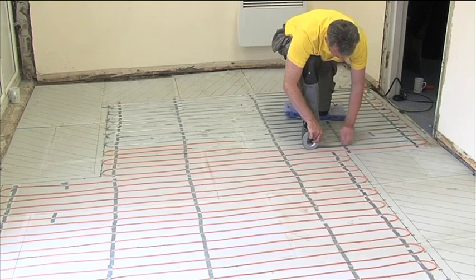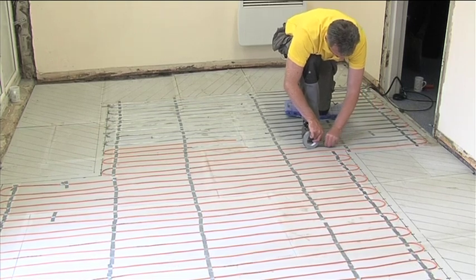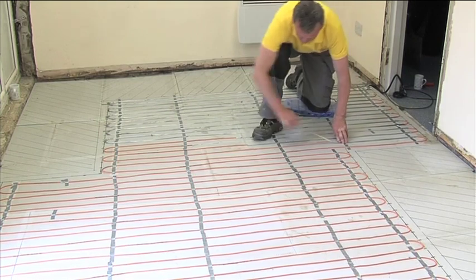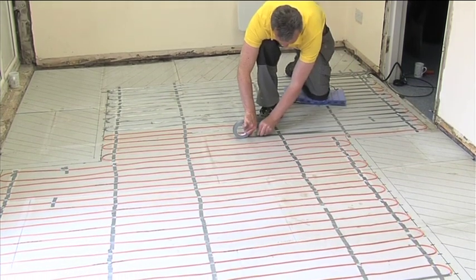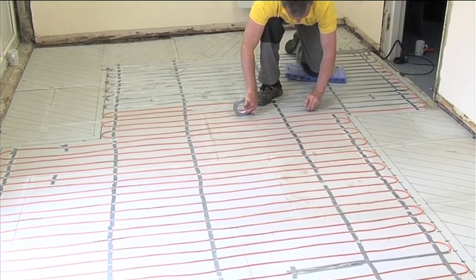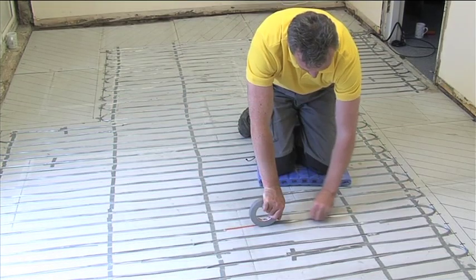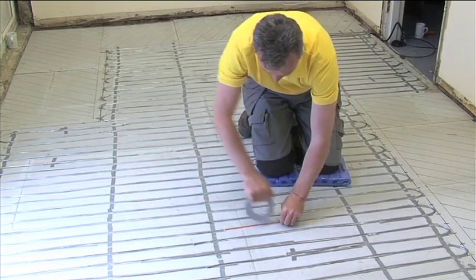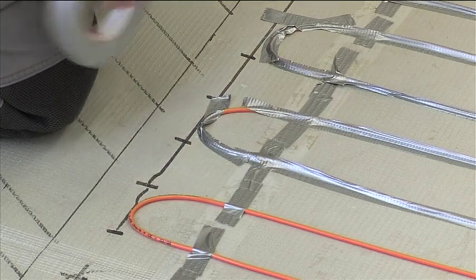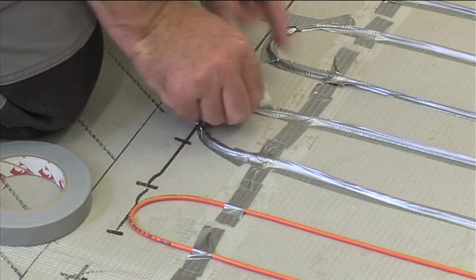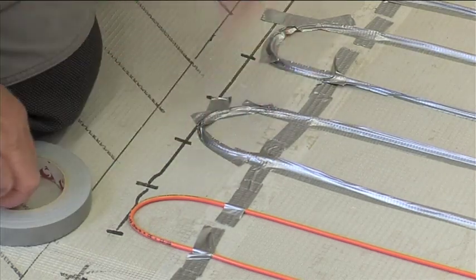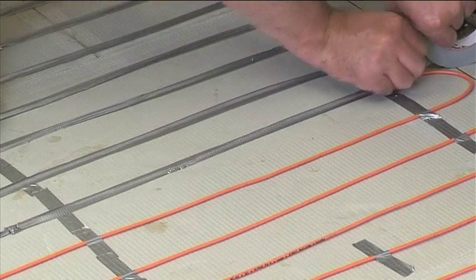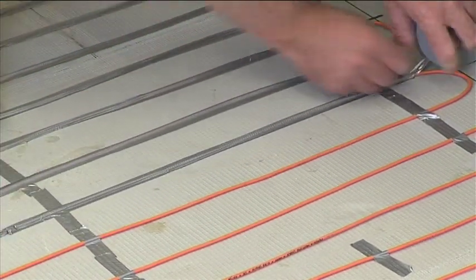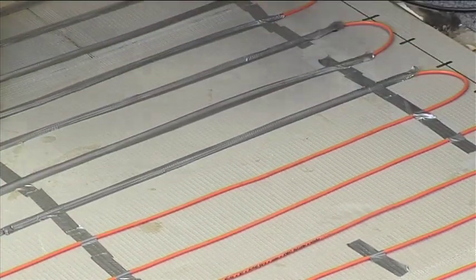Once the cable layout is complete, the entire length of the cable should be taped to the floor. This taping process will provide additional protection to the cable and prevent movement when applying the tile adhesive. When applying the tape, it is important to minimise the amount of air trapped between the tape, cable and the floor. Run your forefinger and thumb along the length of the cable, applying slight pressure to expel any trapped air.